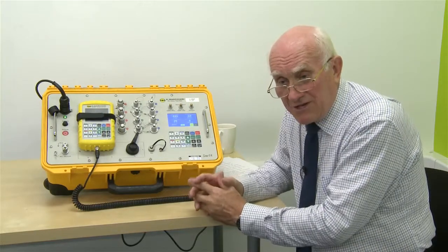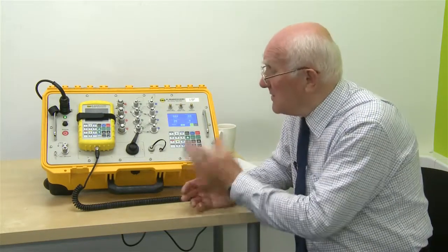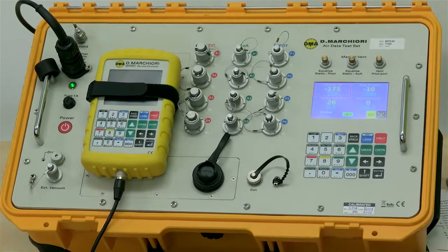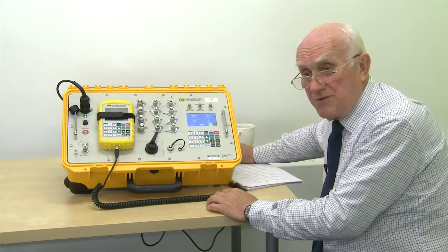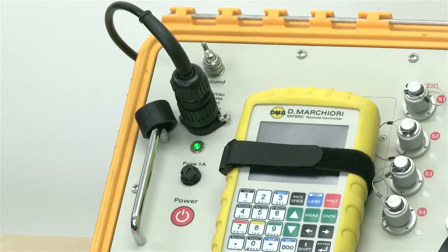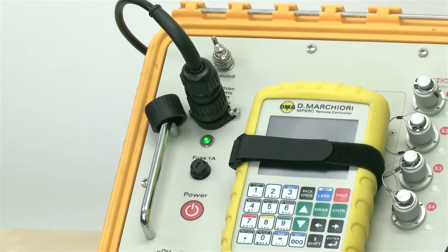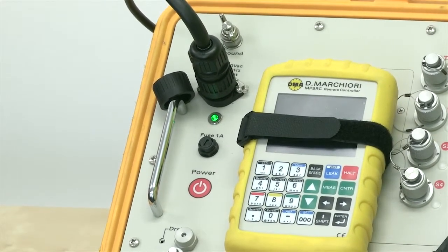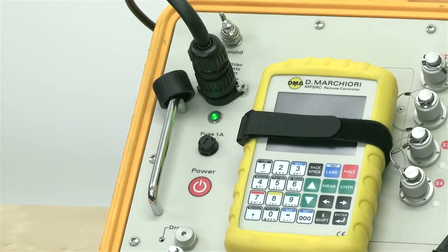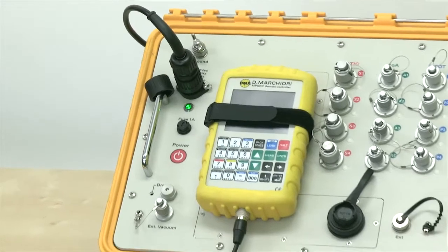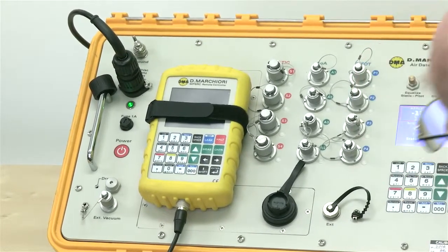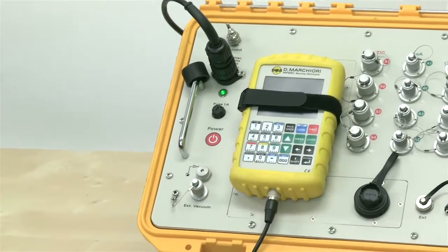Okay, what we're going to do now is go on and talk about the instrument, generally speaking, on the front panel. So let's start looking at what we have on the front panel, just to make sure it's fully understood. We have the AC input. That will run from any of the international voltages and frequencies you can probably think of. We go from 90 volts to 260 volts and something like 40 hertz to 440 hertz. So you're going to be able to run the equipment either on aircraft supplies or indeed on national supplies. You can also, as an option, have in addition a 28 volt capability if you wish, but that's an extra and it's an option. Moving on from there, we have the conventional things like the fuse, the power switch, etc.